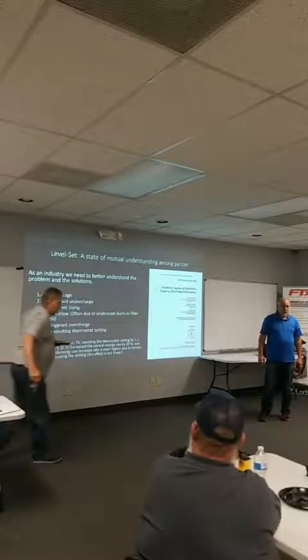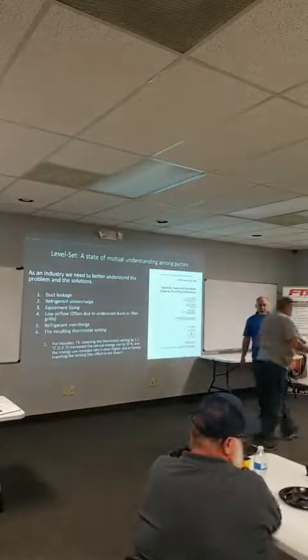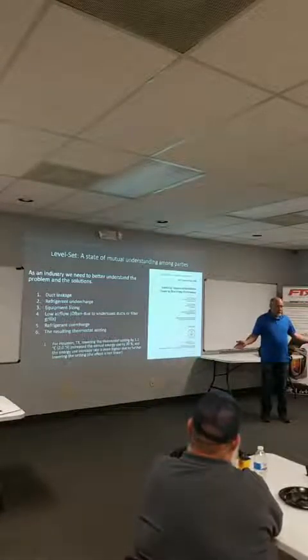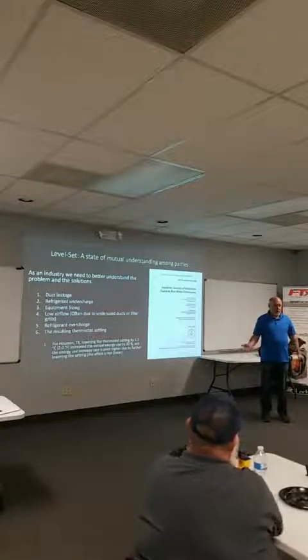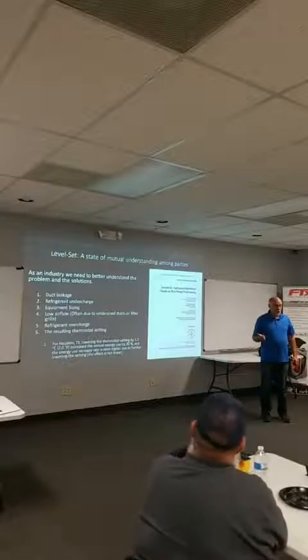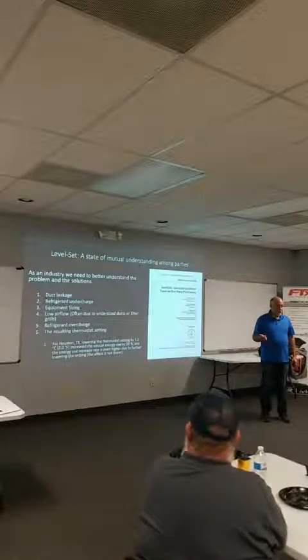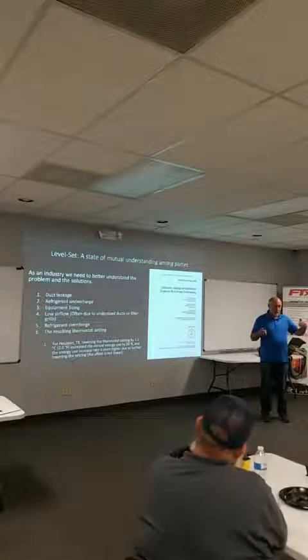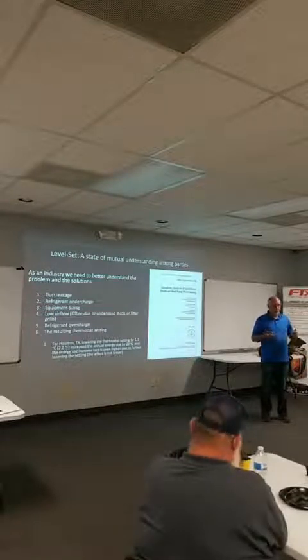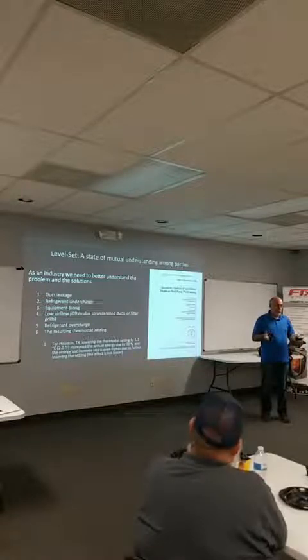Because for a homeowner or a business owner, the only control they have to interface with is the thermostat. If it's not comfortable, they're gonna turn it down further. Guess what happens? There's what's called a balance point. What's the balance point on a system? On any system, we have a balance point. Anybody know? The balance point is when the rate of heat absorption in the building is equal to the rate of heat rejection that the air conditioner or heat pump is capable of doing. The heat exits the building at the same rate we're putting it in. That's the balance point, right? You can have a balance point on either one.